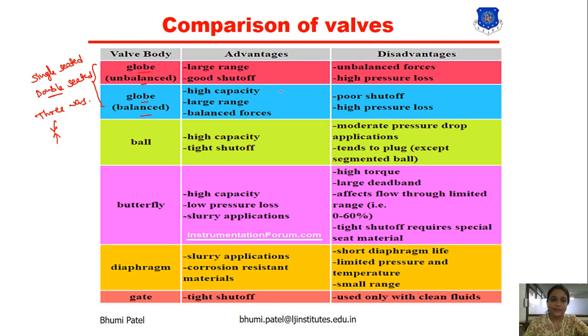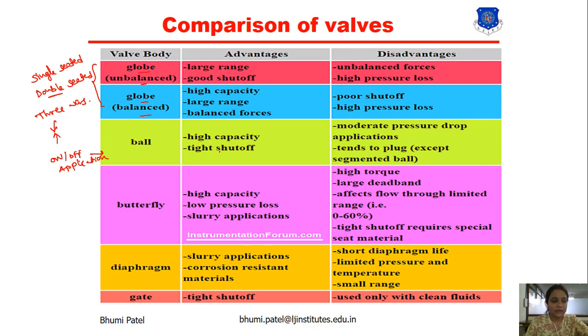One main disadvantage of the globe valve is the high pressure loss. Next is the ball valve, which is generally used for on-off applications. Its advantage is high capacity and tight shutoff. The disadvantage is moderate pressure drop application and it tends to plug except in segmented ball — so it is not recommended for moderate pressure drop applications.